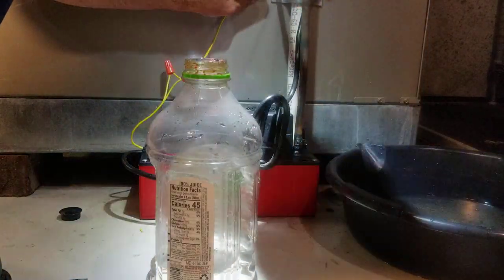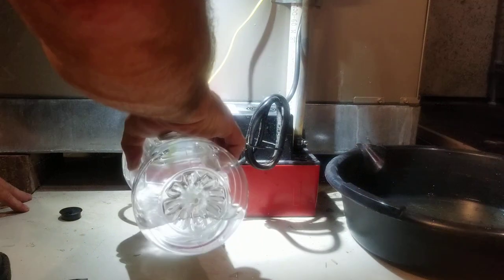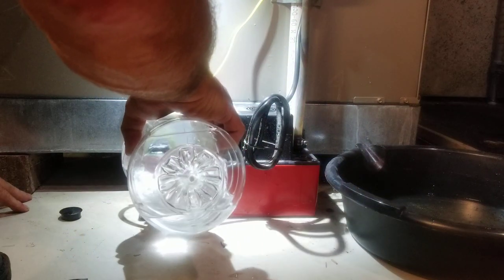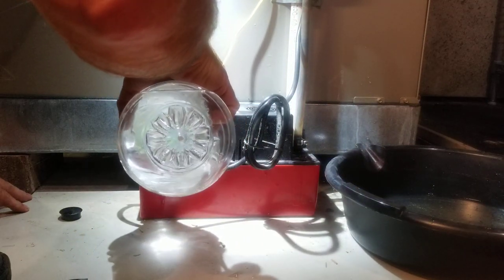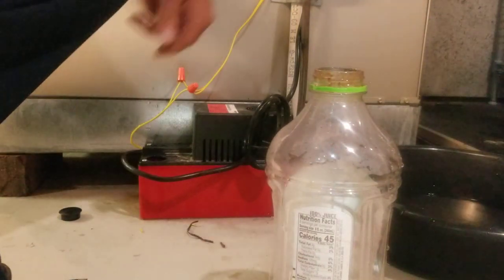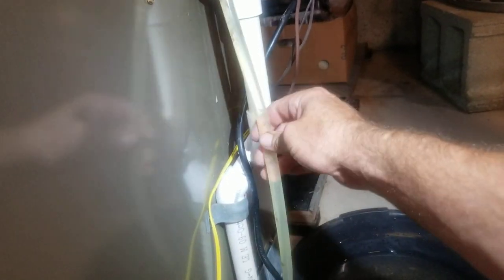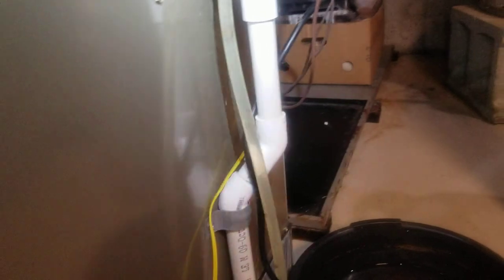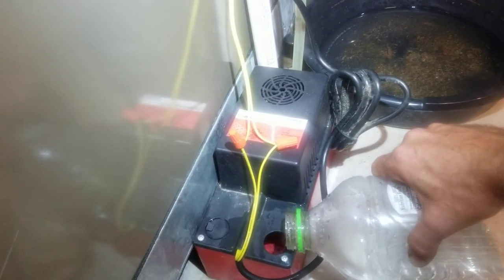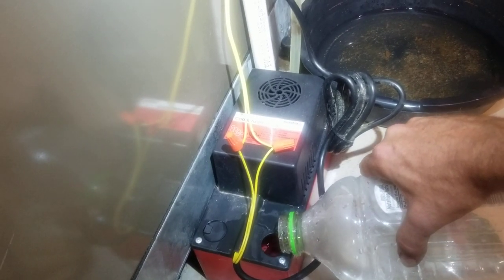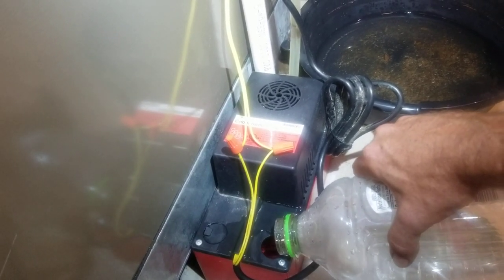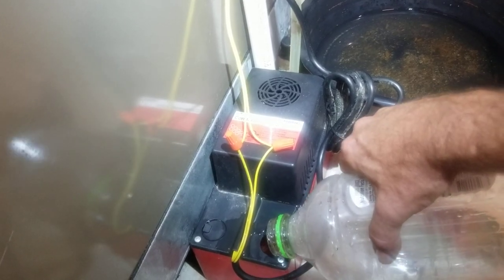Okay, so she's pumping. Keep on flushing it. I want to flush that coil cleaner through here. So I'm going to run, I don't know, three of these. Okay, got it flushed out. You can see my line's clearing up with that coil cleaner. You gotta run extremely hot water through here, and if you do that, you get it all cleaned up. I must have flushed about four of these through there just to work that coil cleaner through the line, flush it out, make sure everything works.